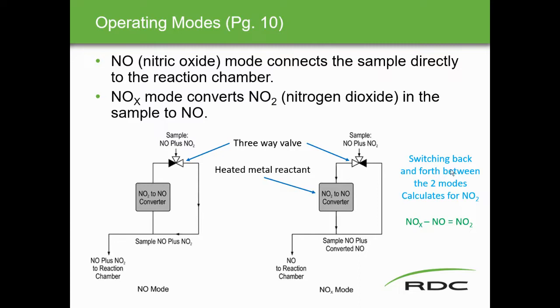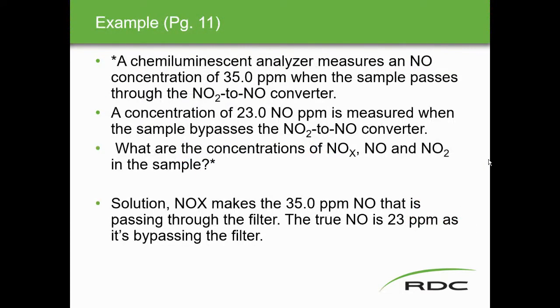As an example: if the NOx reading is 35 ppm (sample through converter) and the NO reading is 23 ppm (sample bypassing converter), then NO2 = NOx − NO = 35 − 23 = 12 ppm. The calculation is a simple mathematical subtraction, and the formula is provided on page 11 of the course notes.